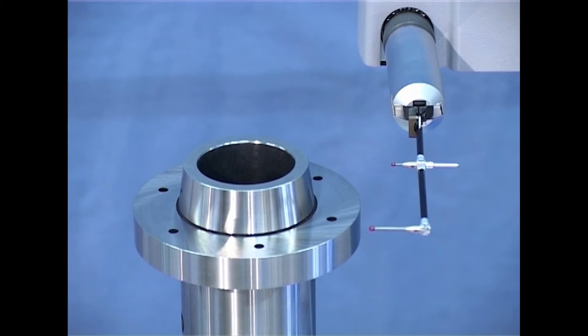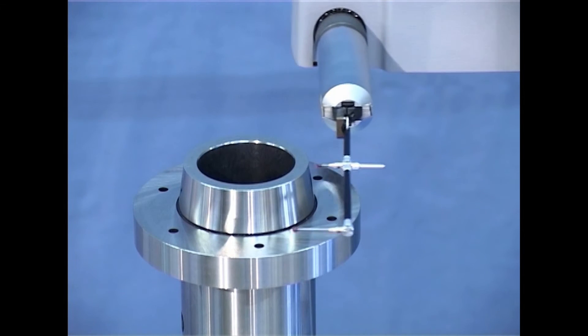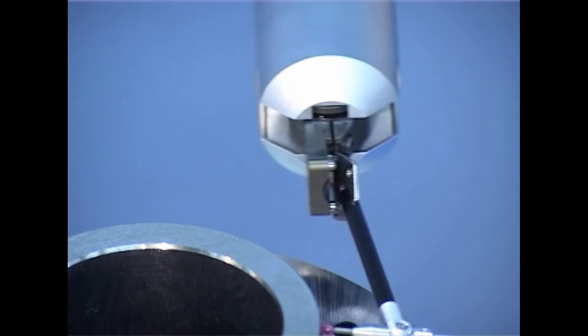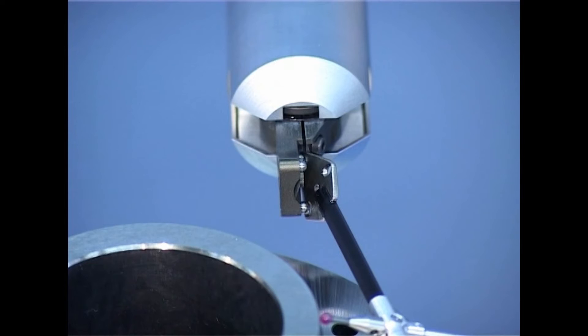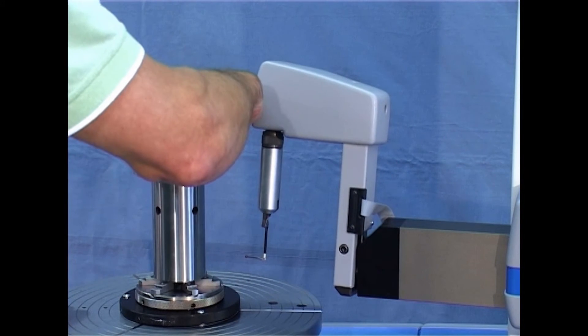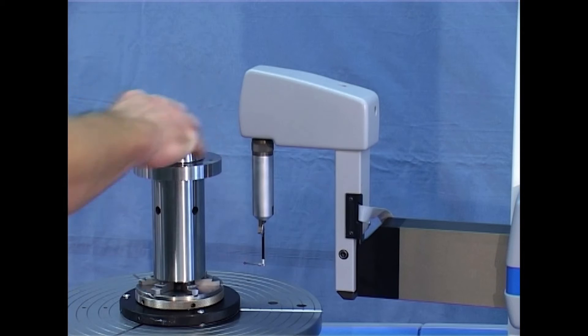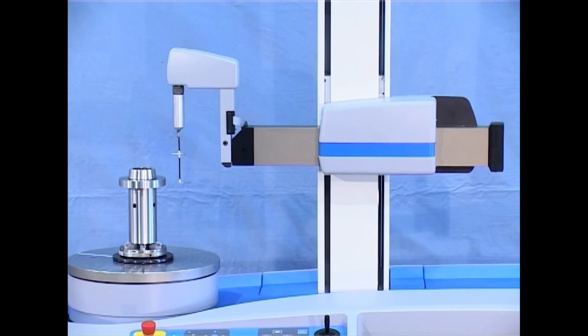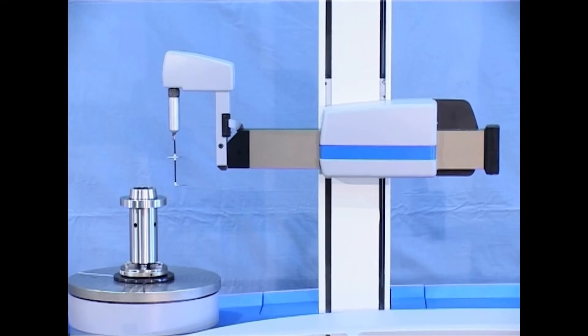The sophisticated collision protection guarantees impressive safety. Magnetically coupled probe arms simply click out in case of collision. The automatic rotation and tilt module stops the axis immediately in the event of a collision, and the R and Z axis are equipped with an overload protection.